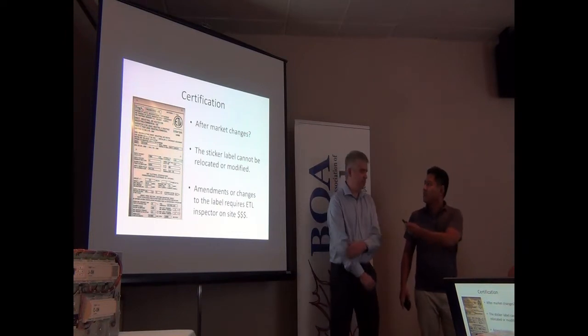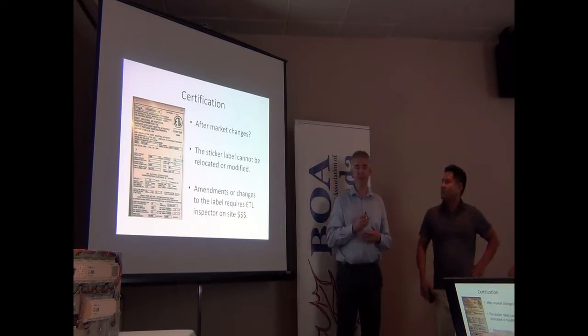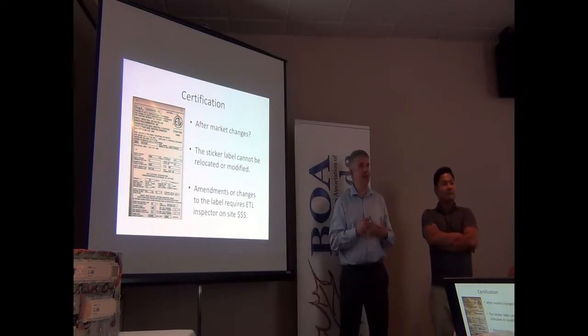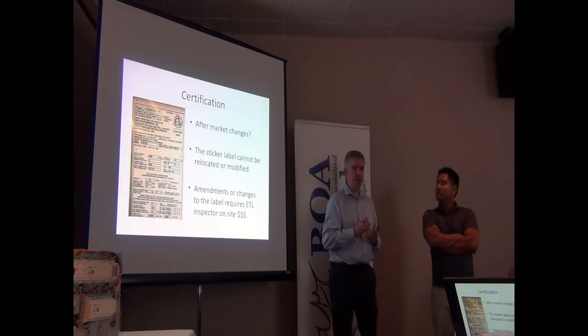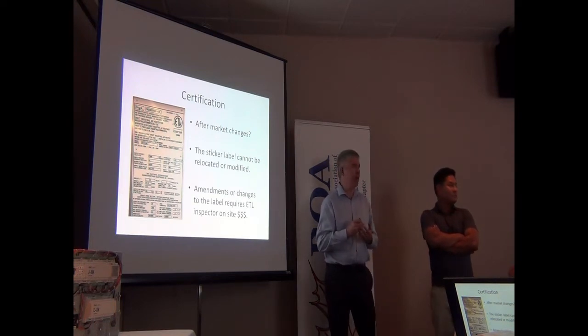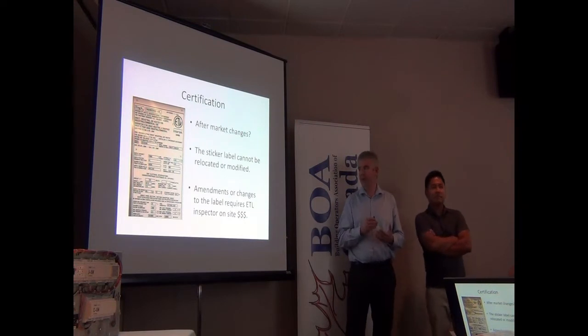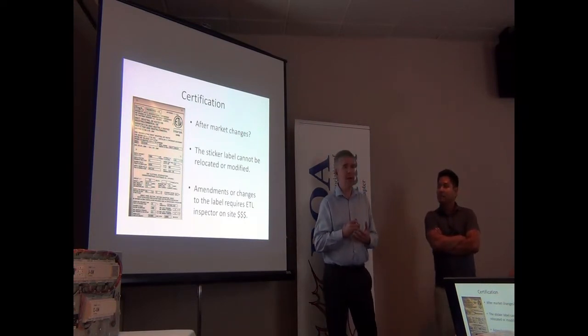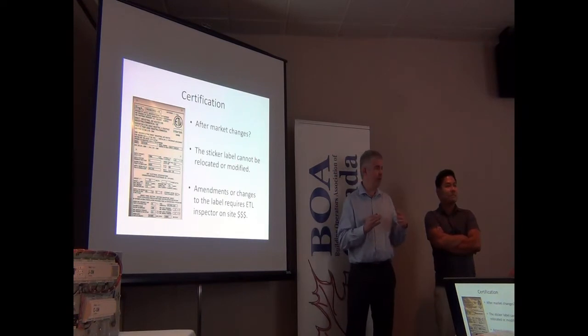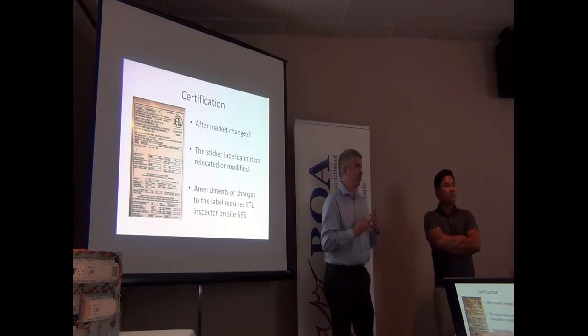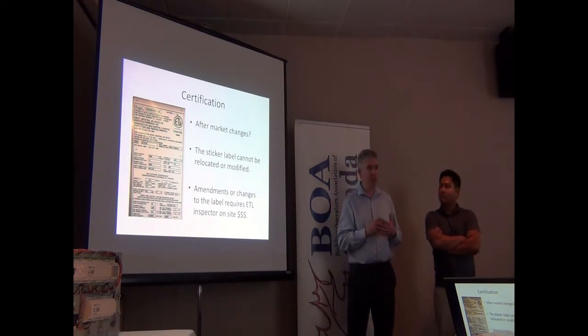Got anything to add? Sure. There are always certain types of changes that could be done outside of units. Some people want to change filtration, for example—that's pretty easy. Or maybe you want to add a coil, or change some ductwork. Things like that outside of the unit are certainly possible. But the more things you start altering outside of it, the further you move away from what it was designed to do, in terms of the fan operating curve, the air actually being supplied, and potentially the horsepower of motors involved. So generally, try to find the unit that suits your purpose. If your purpose has changed, find something suitable for that, and hopefully don't try to modify it too much after the fact.